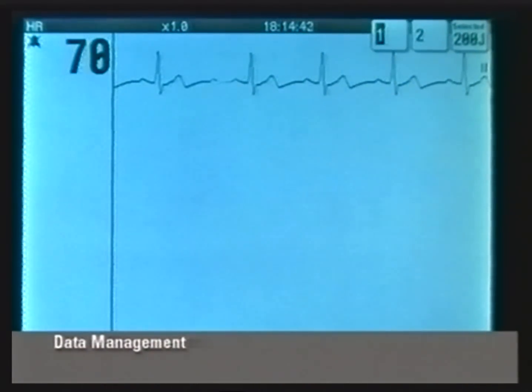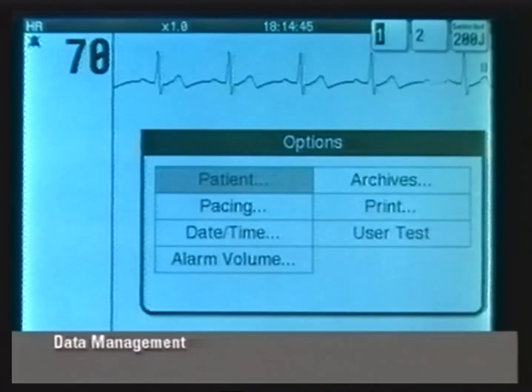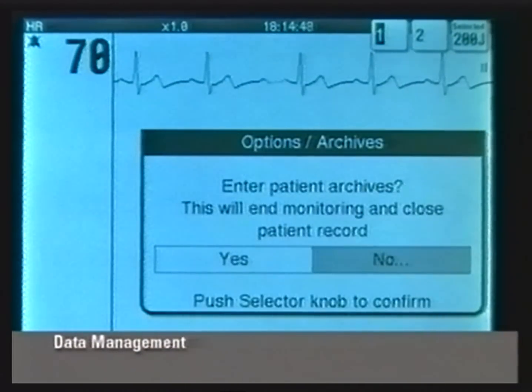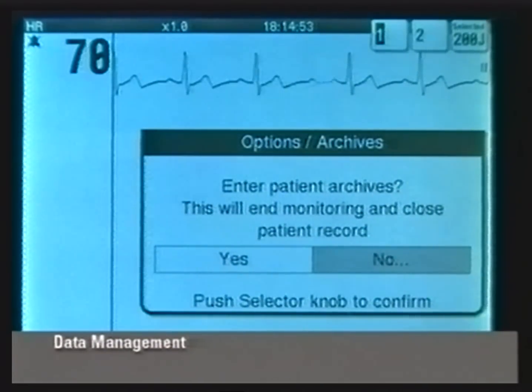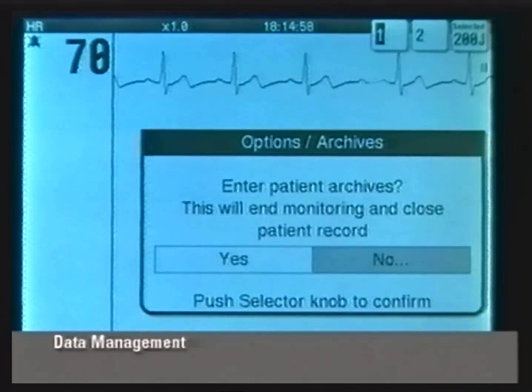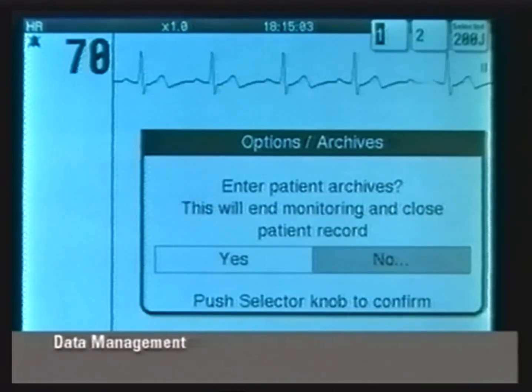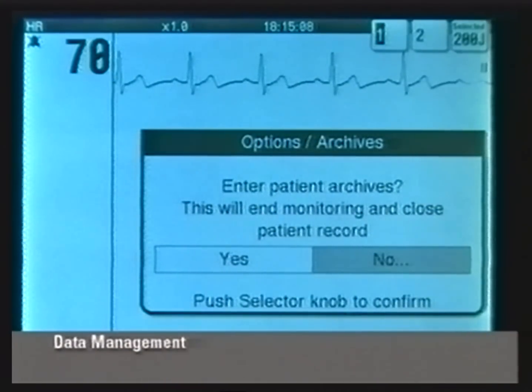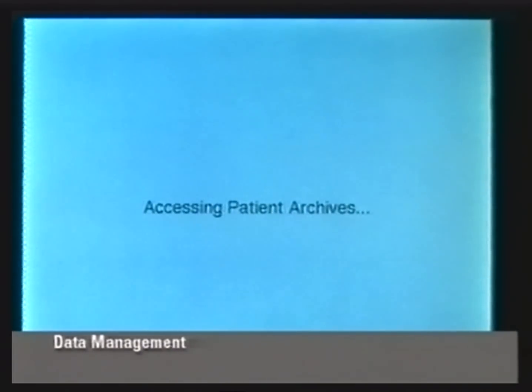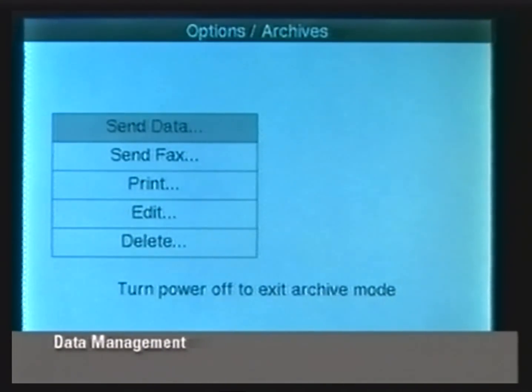To access archived patient records, press Options and select Archives. If you enter Archives mode during patient monitoring, the current patient record will be saved and the Lifepak 12 defibrillator monitor will restart in Archives mode. You will not be able to continue monitoring, all therapy will be discontinued, and alarms will be disabled. To confirm that you want to enter Archives mode, select Yes to save and close the current patient record and enter Archives mode. 5 choices will appear.